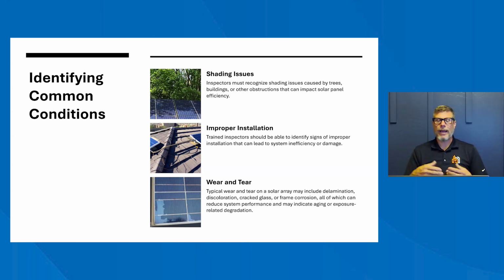Look for faded or missing labels, cracked conduit, and corrosion around the frames and fasteners. These are normal signs of aging, but they're all worth calling out and need to be reported, especially if it's a leased system. We don't always know that in advance, so always walk into these inspections assuming it's leased, since that's typically most common. Call those issues out so the leasing company can come out and correct them, taking these small issues and preventing them from becoming big issues.